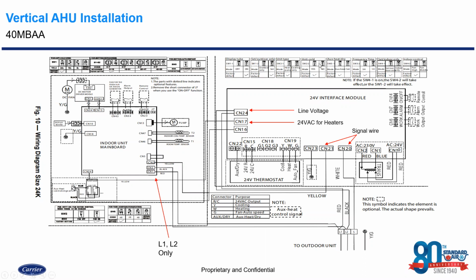Okay, and if you look to the right here, we have SW21, 22, 31, 32, 41, and 42. Now, depending on the specifics of your application is going to determine whether you need to flip these dip switches on or turn them off. Typically, what I tell guys is they should all be in the off position unless you have a particular need. So for this example, you'll see here SW31. Do we have auxiliary heat? Well, yes. Okay, well, SW31 needs to be in the off position so that the interface knows that it has auxiliary heat. And when that control signal is sent to CN22, this interface responds properly and sends that 24 volts AC control signal to turn on that auxiliary heat, depending on what we set that threshold for.